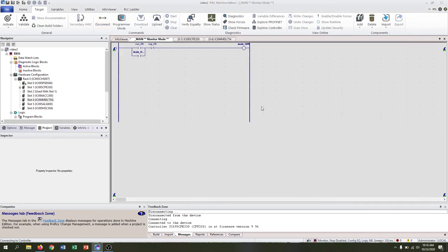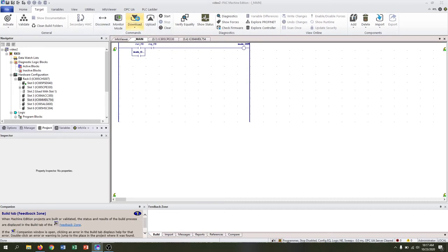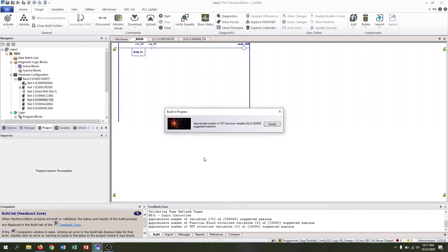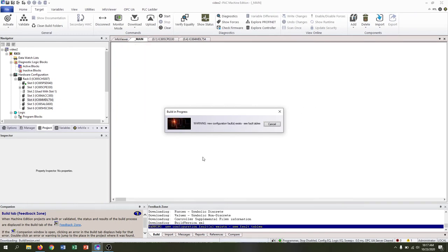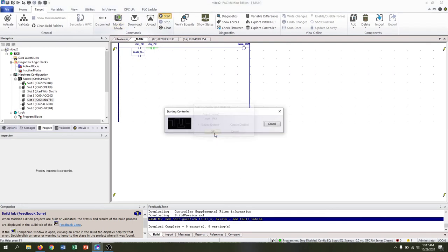And if we look, we need to make sure that we go back to programmer mode. Our configuration is equal, but our logic is not equal because we changed our program. So make sure it's stopped and we can download to the target. We'll hit OK. And if you look at our configuration now, looks like we have a fault.